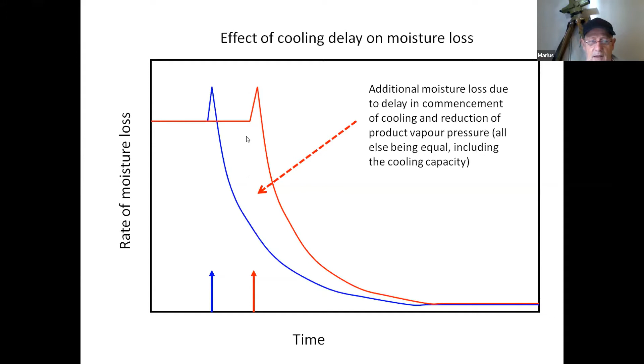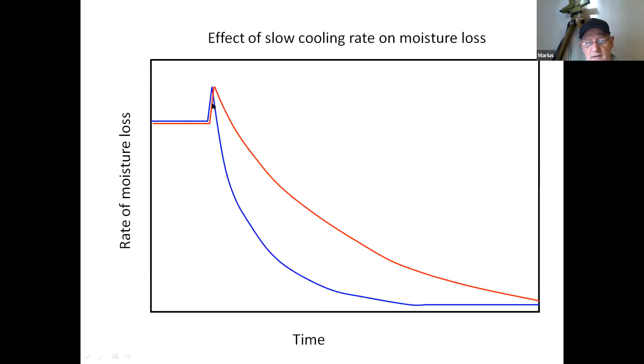Looking at the effect of the cooling rate, this is where the size of the system comes into play. Are you trying to cool a lot of fruit with a small system, or is it an adequately sized system? That would be the standard, the blue line. If you have a smaller system that's incapable of maintaining the correct temperatures or getting rid of that heat load, you have the red line, which just represents a much slower rate of cooling, which gives you that higher rate of moisture loss for a longer period of time. Then the difference between the blue and the red line, this whole area, represents the additional moisture loss that you would have because of the slow cooling and the slow reduction of that product's vapor pressure. So your VPD remains high because of the fact that your product is not cooling fast enough.